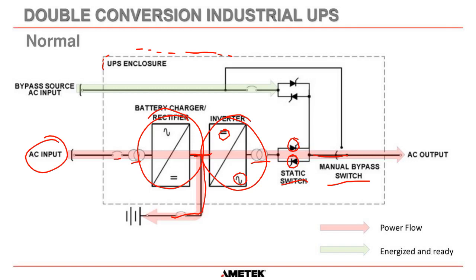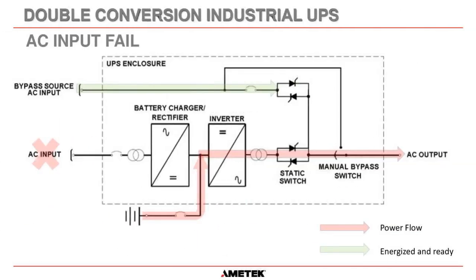But it is completely different from the manual bypass switch. The manual bypass switch is an actual physical rotary switch that somebody has to go and turn manually, okay? There is no automatic function on the bypass switch itself, the manual bypass switch. It has to be turned by an operator, okay? So it's a big difference between the static switch and the manual bypass switch. And then obviously we have the bypass static switch up here ready to turn on if necessary. And on the next screen, you'll see when that would happen. Well, in the next few screens.